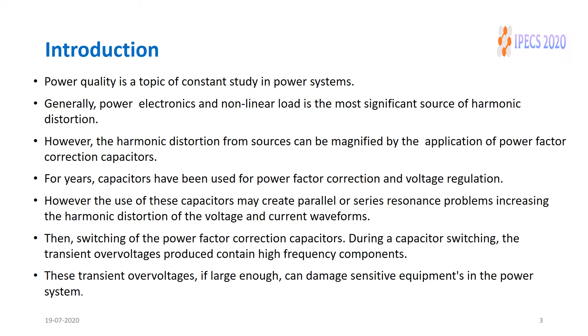If these transient over voltages are large enough, they can damage sensitive equipment, like protective equipment or the power electronics converters used in the power network. So this is the major issue of the power network when we use power factor correction capacitors. What is the objective of this paper? This paper addresses the transient over voltage and the harmonics induced by capacitor bank switching in the power system.